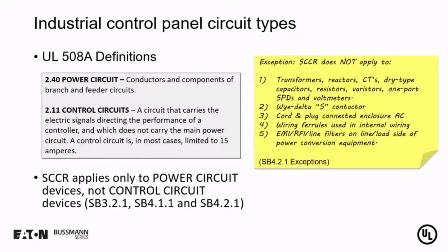There are some exceptions to devices that do not have an SCCR. Things such as transformers, for instance, dry type capacitors, one-port SPDs, wye-delta contactors, cord and plug connected enclosure ACs, wiring ferrules, and filters when used with power conversion equipment.